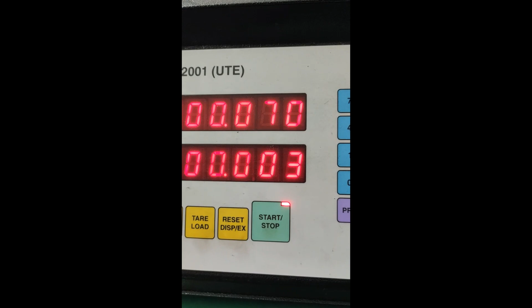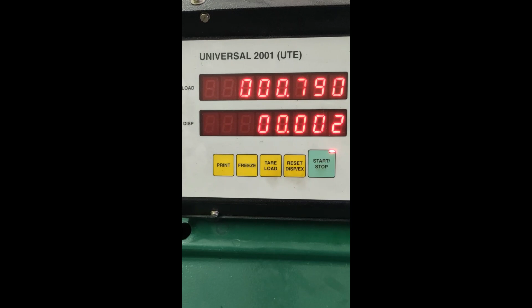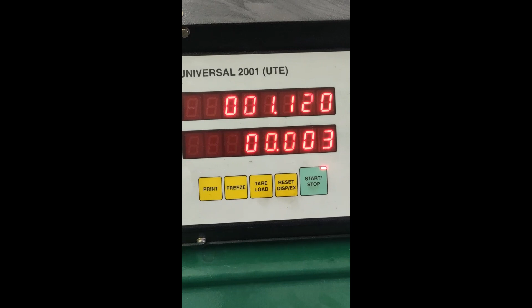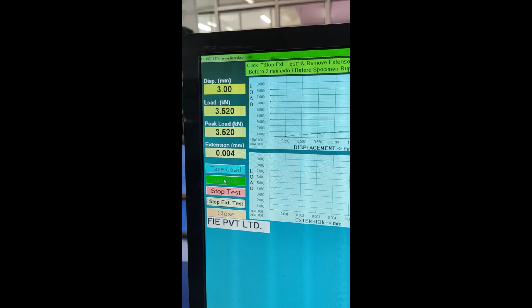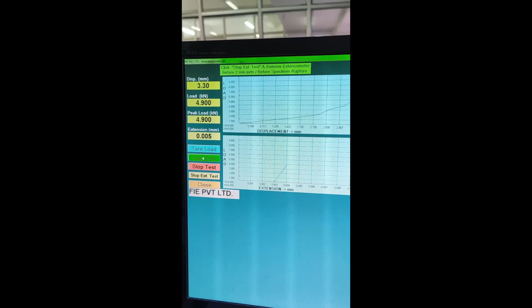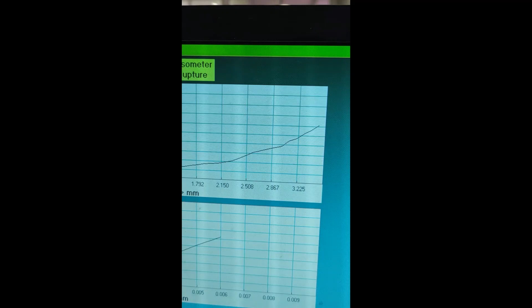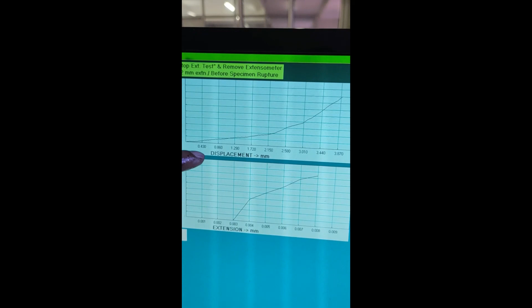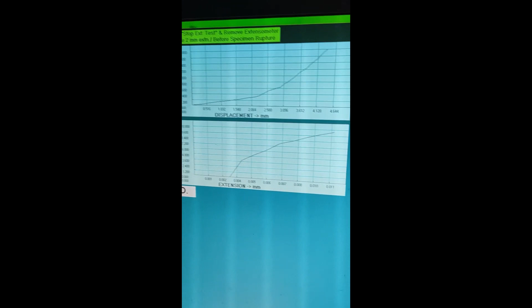Once the load reaches, suppose, 1 kilonewton or 2 kilonewton, maximum 5 kilonewton, then we will release this. This way it will continue. So we will show you how it is going on. Now the load is showing 1.4, and it is increasing. In the software you can see load versus displacement, and on the other side load versus extension. Load comes from the load sensor and displacement comes from the linear encoder, as I told, and this side is also load versus extension. Extension means the extensometer reading.